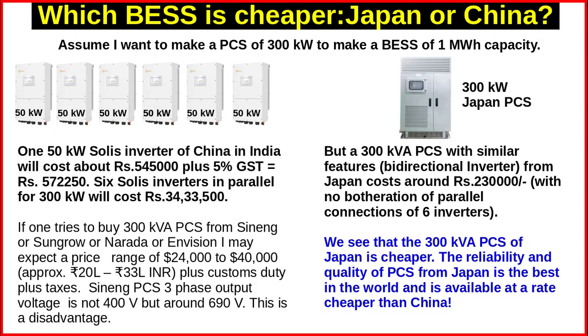Which BESS is cheaper, Japan or China? To know this, let us take an example. Assume that I want to make a PCS of 300 kilowatt to make a BESS of capacity 1 megawatt hour. So if I want to do it from the China models, what is available in India, and if I select Solis inverters, the maximum power available in Solis inverters in India is only 50 kilowatt per box. So to achieve 300 kilowatt, I will have to parallel 6 number of 50 kilowatt PCSs.